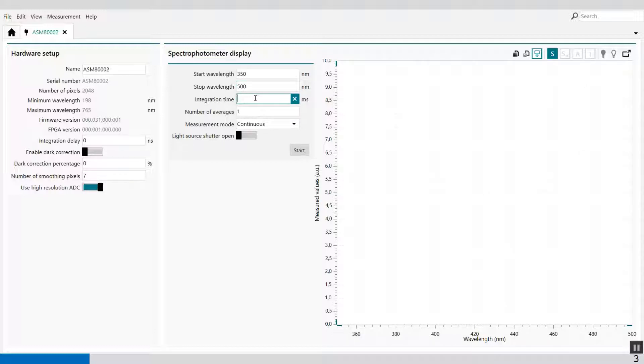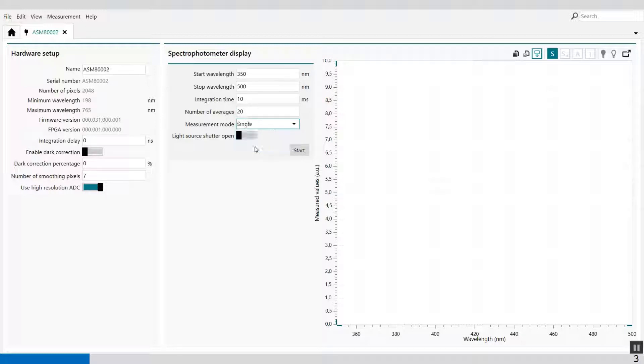The integration time is an input field which can be used to specify the integration time; the smallest possible value is 1.1 milliseconds, while I'm taking an integration time of 10 milliseconds. Number of averaging is also an input field to specify the number of average spectra as an integer — let's say 20. Then the measurement mode can be continuous or single; in this case I'm going to set it to single. With the light source shutter open or closed, I can define the shutter control.